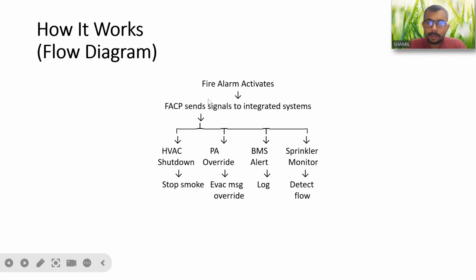Whenever a fire alarm gets activated, it sends signals to the integrated systems. The HVAC system will shut down, the public address will override, the BMS will send an alert, and the sprinkler system will be monitored. In case of any water movement or tampering, the flow monitor module associated with the sprinkler system will communicate to the control panel, which will initiate the necessary alarm or supervisory signal as per the client requirements.